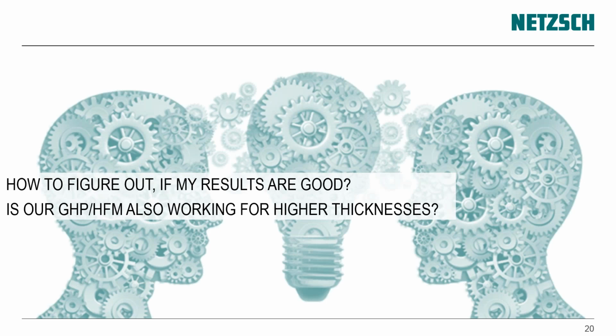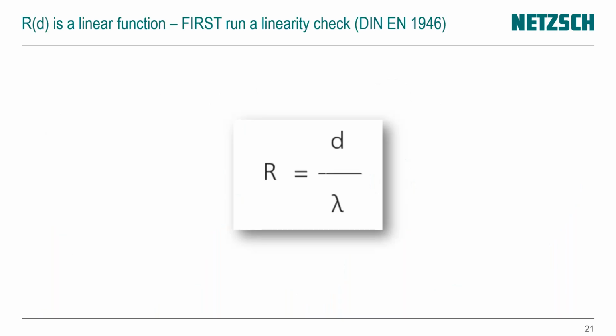How do I figure out if the results that I get from the instrument after a proper calibration are good? There is something that we can learn from the guarded hot plate field, which is a similar method, but an absolute method, where there's no need for calibration. It's quite simple. To check if a heat flow meter works in the range of thicknesses and the ranges of materials that you want to measure in your daily quality control, you can run at first a linearity check. What is a linearity check?